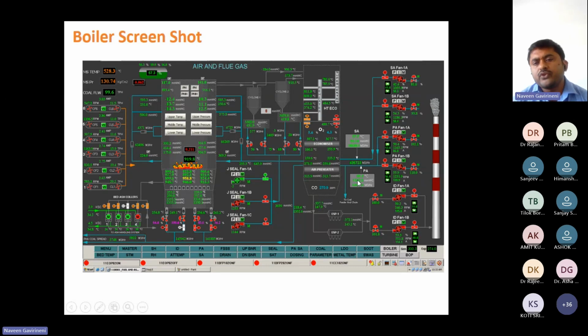Suppose you consider this PA fan, there is combustion happening at this place. There is a chance of finer particles escaping. If the finer particles escape, our coal is going to be wasted at the outside, and the LOI, loss on ignition, is also going to increase. For that purpose there is an arrangement, which is nothing but tertiary combustion. So we are supplying air at this place. Complete combustion happens. This is the concept of CFBC. Actually, we have different technology arrangements. From a combustion point of view, for medium capacity, CFBC is the best option. This will give combustion efficiency of more than 99%.